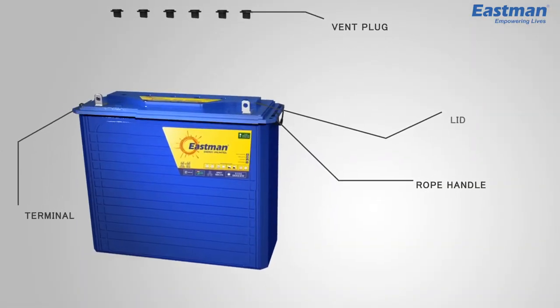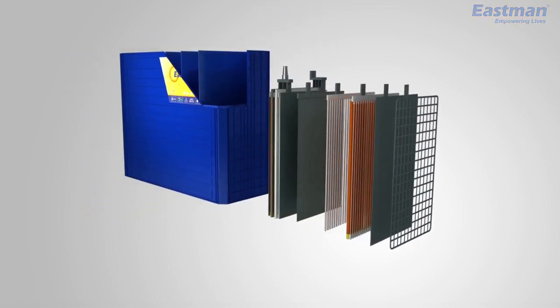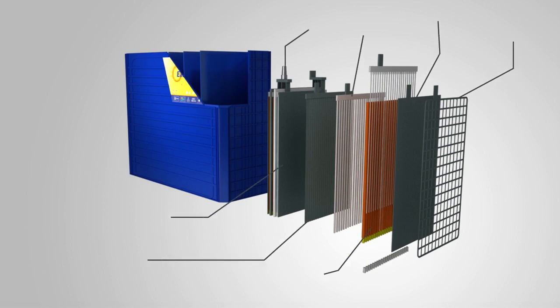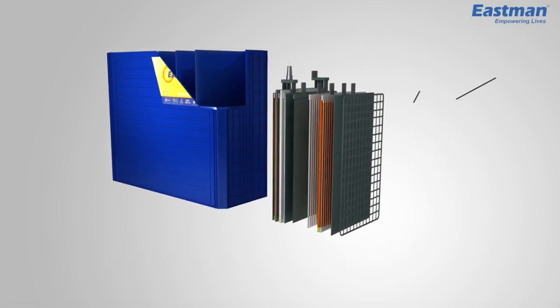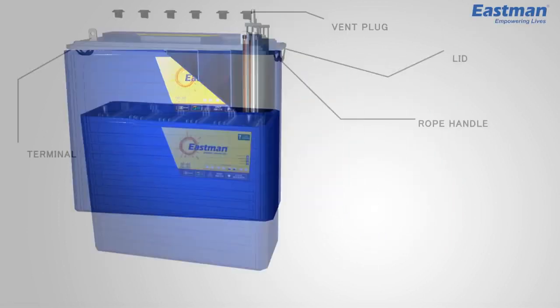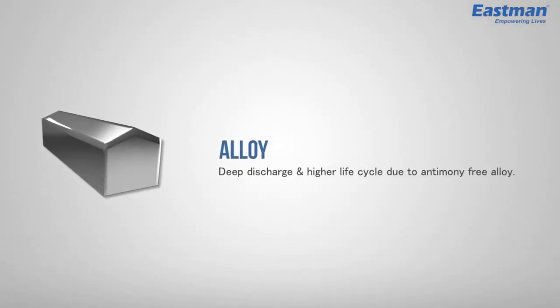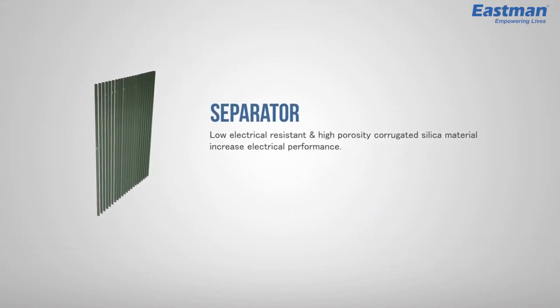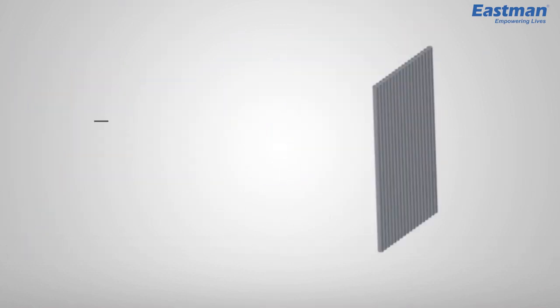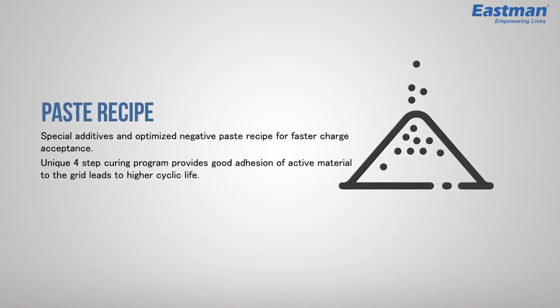What is tubular gel technology? A modern gel battery, also known as a gel cell, is a VRLA battery with a jellified electrolyte. The sulfuric acid is mixed with fumed silica, which makes the resulting mass gel-like and immobile. Unlike a flooded wet cell lead-acid battery, these batteries do not need to be kept upright. Tubular plates use a frame structure consisting of a series of vertical spines connected to a common bus bar. The tubular design keeps the active material mechanically together inside the porous gauntlet and around the spines.